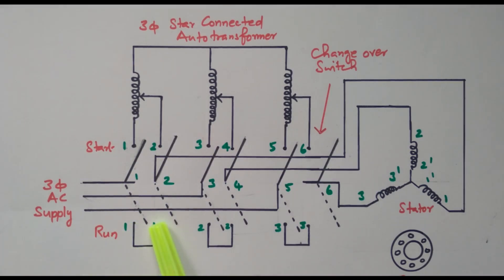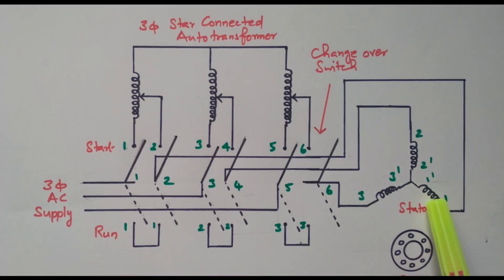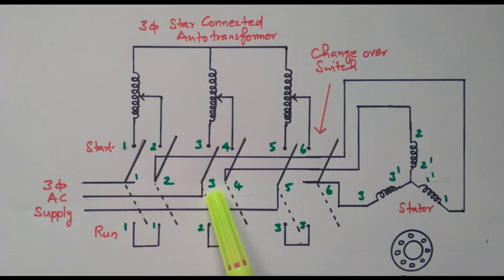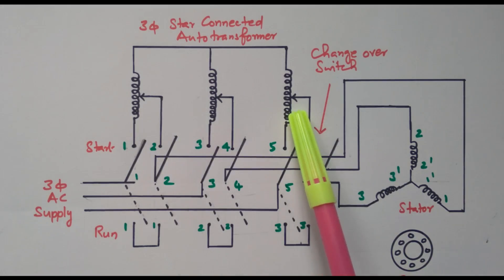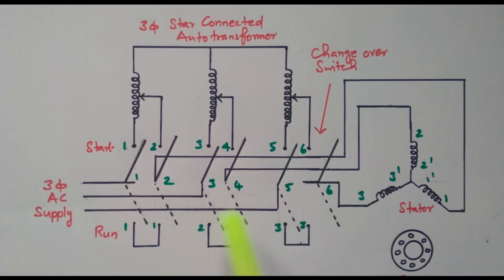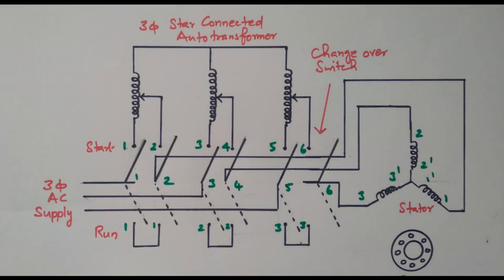The run position is simply a short circuit where the entire voltage is applied. We have a three-phase AC supply, and the stator is connected to the three-phase supply through the changeover switch. The star-connected auto-transformer is available at one end, and the other end is short-circuited. This end is called the starting position, and the other is the running position.